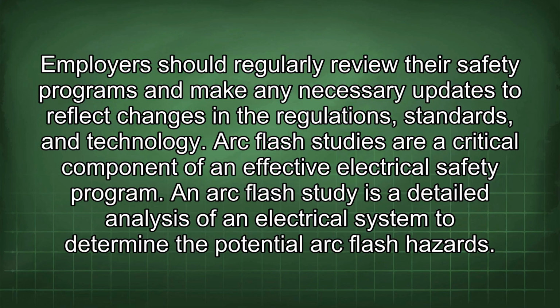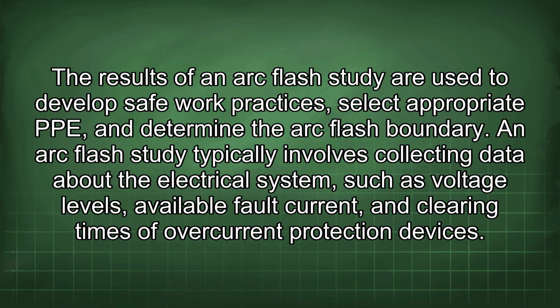Arc flash studies are a critical component of an effective electrical safety program. An arc flash study is a detailed analysis of an electrical system to determine the potential arc flash hazards. The results of an arc flash study are used to develop safe work practices, select appropriate PPE, and determine the arc flash boundary. An arc flash study typically involves collecting data about the electrical system, such as voltage levels, available fault current, and clearing times of overcurrent protection devices.